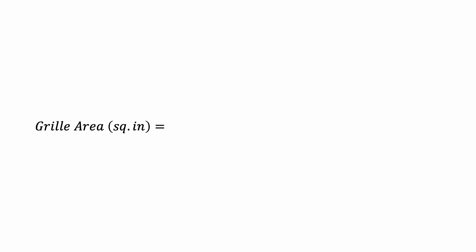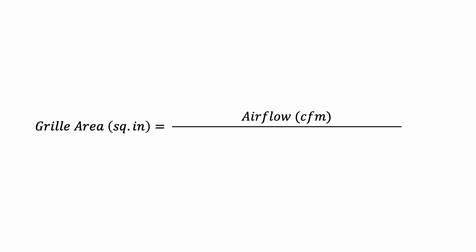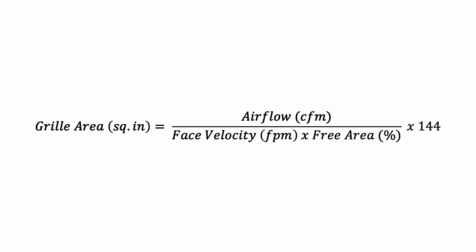Return air grill can be sized using the grill size formula. The formula is: grill area in square inches equals the airflow in CFM divided by face velocity in feet per minute, multiplied by the free area of the grill in percentage, and then multiplied by 144 to convert from square feet to square inches.